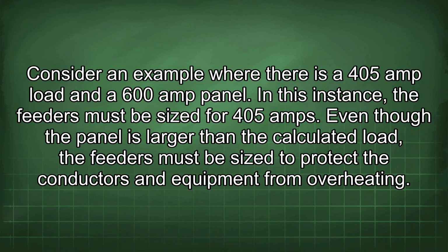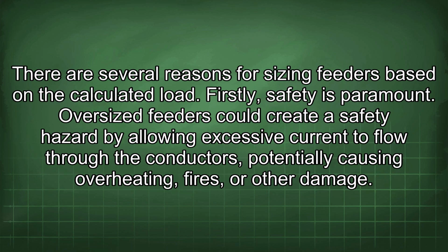Even though the panel is larger than the calculated load, the feeders must be sized to protect the conductors and equipment from overheating. There are several reasons for sizing feeders based on the calculated load. Firstly, safety is paramount. Oversized feeders could create a safety hazard by allowing excessive current to flow through the conductors, potentially causing overheating, fires, or other damage.